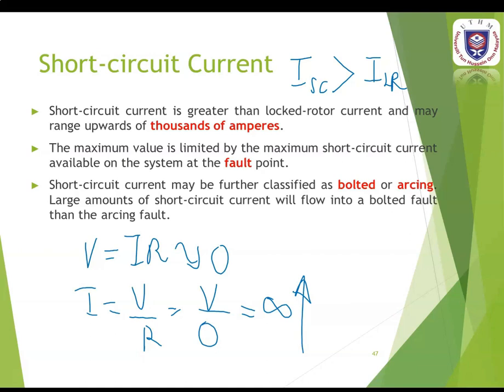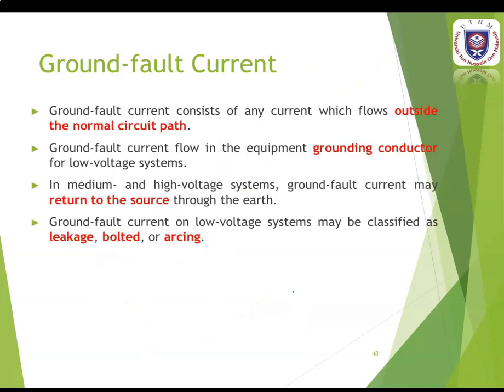By definition, a bolted fault has no fault impedance, while an arcing fault current has impedance associated with the arc. Therefore, the bolted fault has higher fault current magnitude than the arcing fault. Ground fault current consists of any current which flows outside the normal circuit path. Ground fault current flows in the equipment grounding conductor for low voltage systems. In medium and high voltage systems, ground fault current may return to the source through the earth.